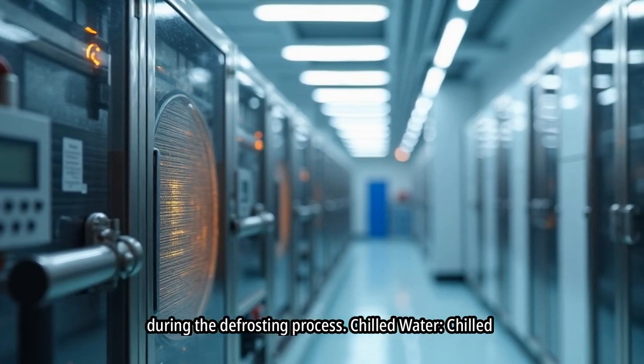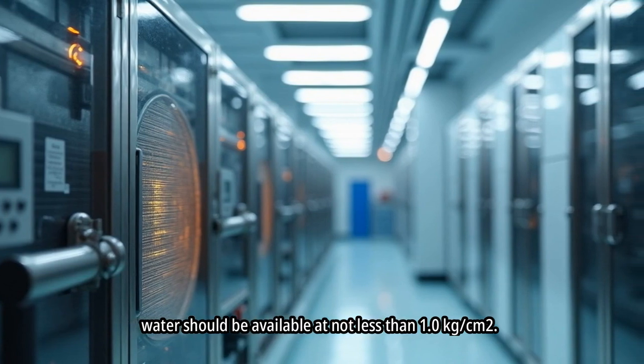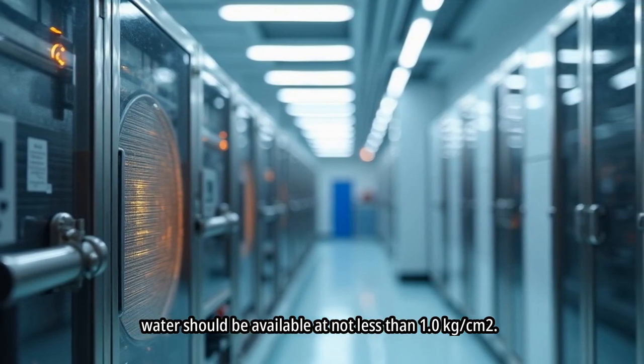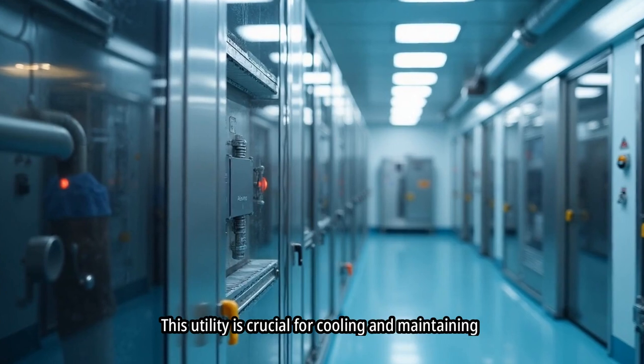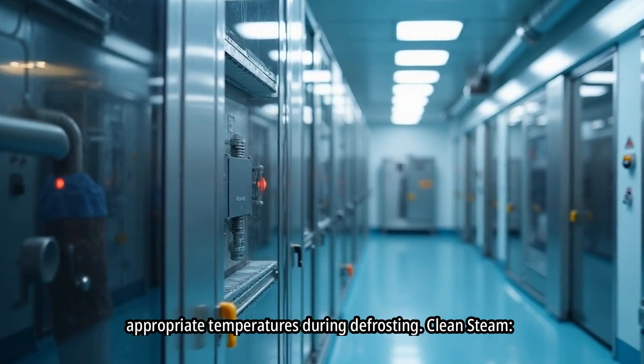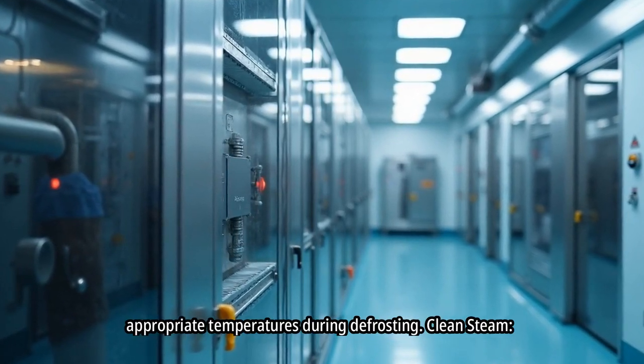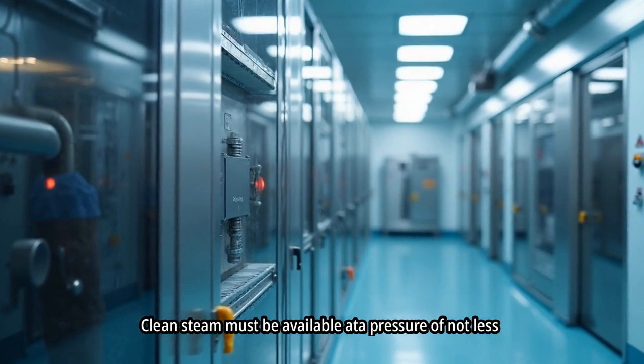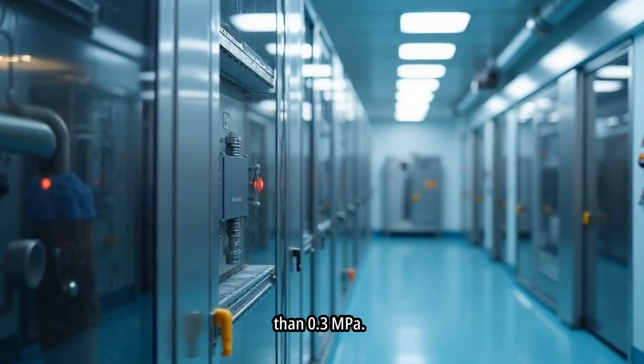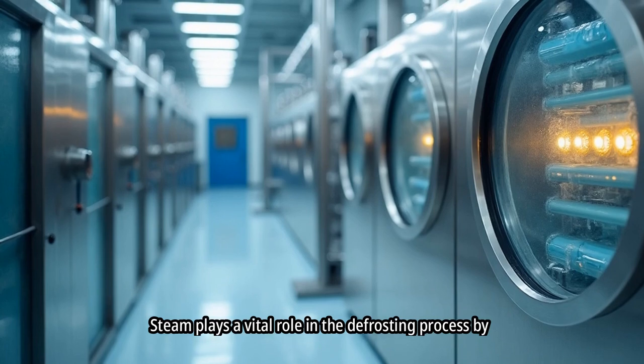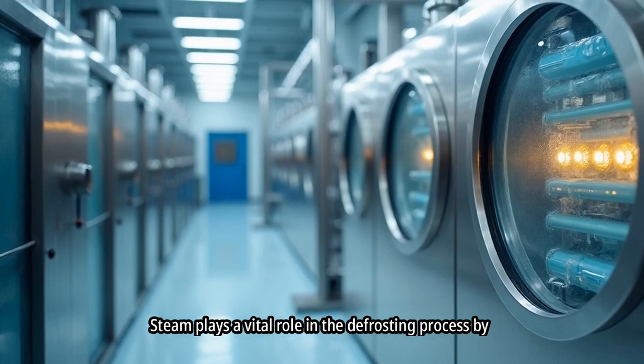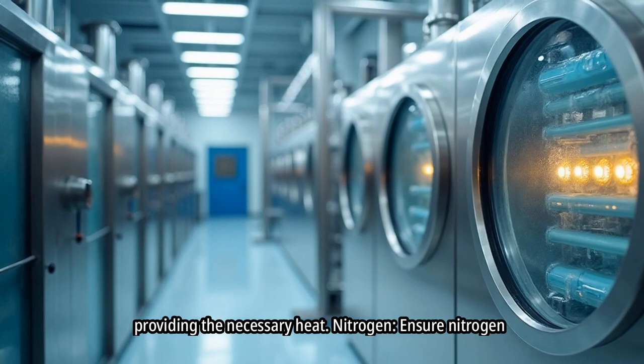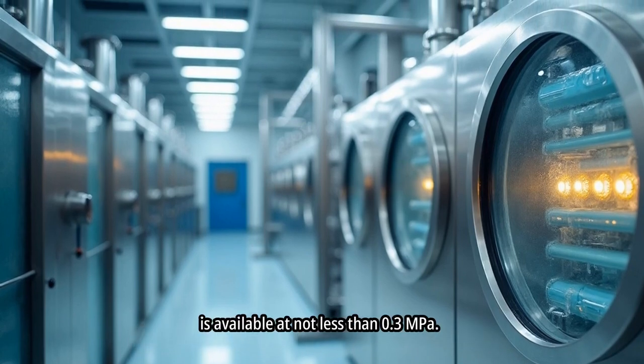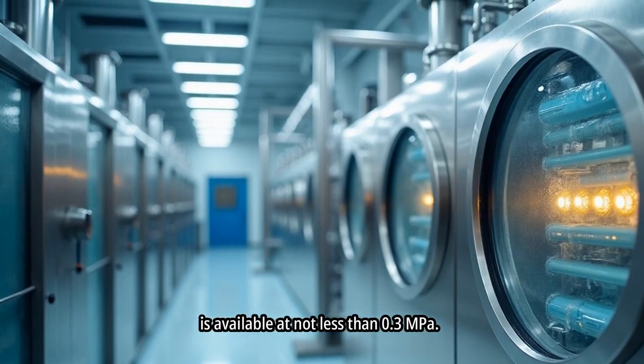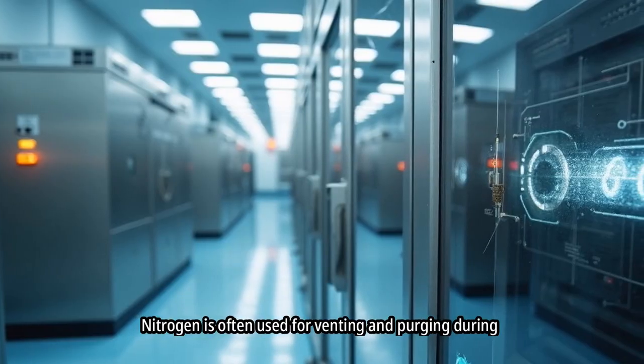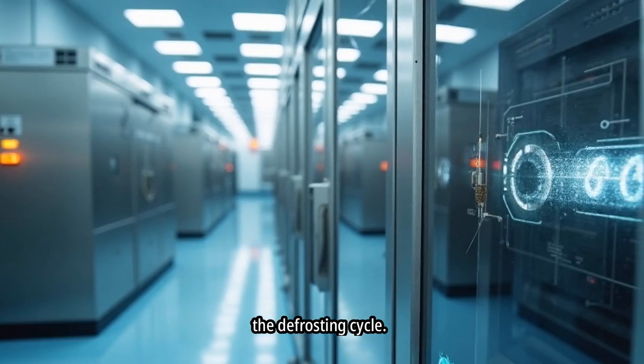Chilled water. Chilled water should be available at not less than 1 kg/cm2. This utility is crucial for cooling and maintaining appropriate temperatures during defrosting. Clean steam. Clean steam must be available at a pressure of not less than 0.3 MPa. Steam plays a vital role in the defrosting process by providing the necessary heat. Nitrogen. Ensure nitrogen is available at not less than 0.3 MPa. Nitrogen is often used for venting and purging during the defrosting cycle.